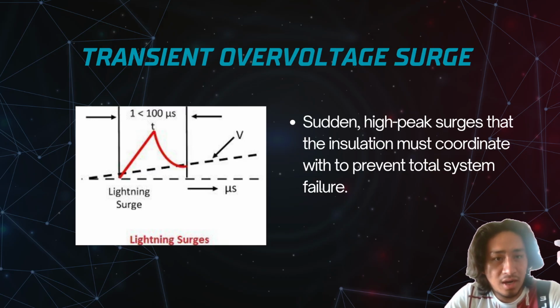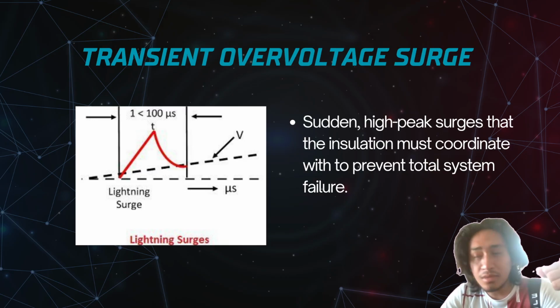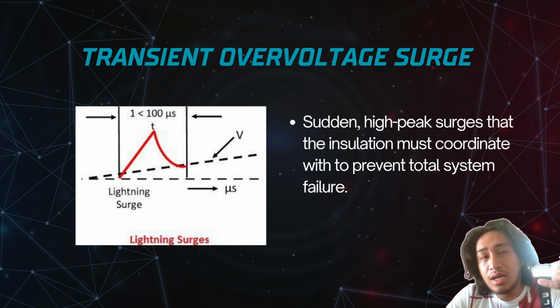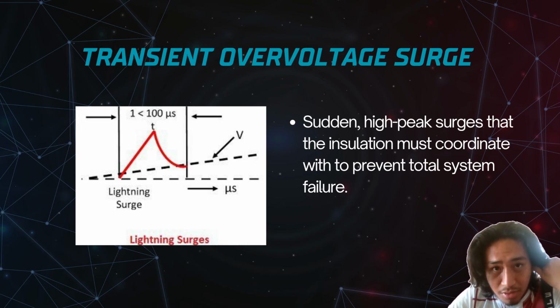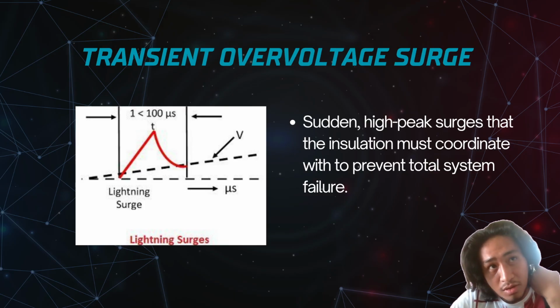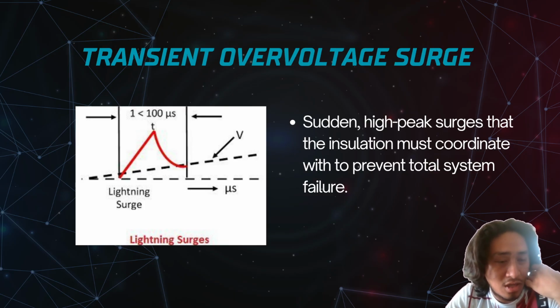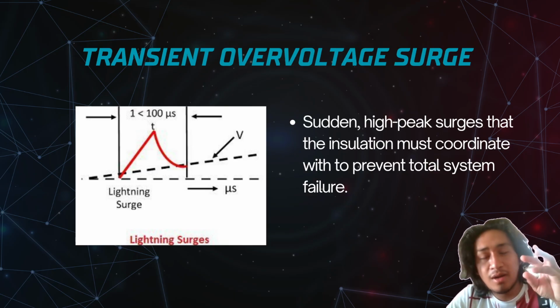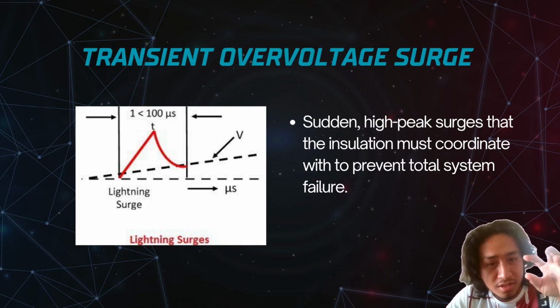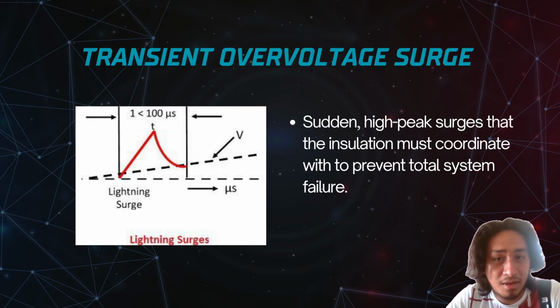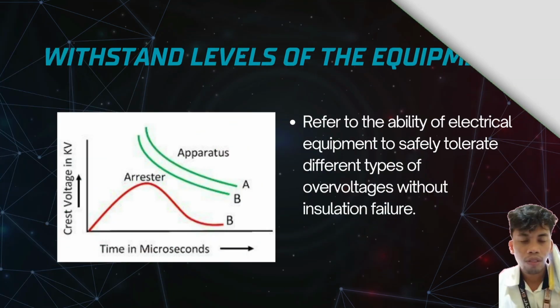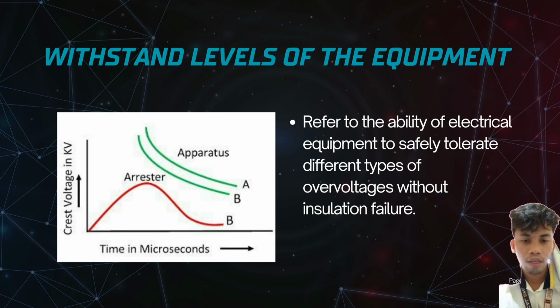So in order for the lightning not to strike the line directly, the tower is equipped with protection called lightning arresters. It is connected directly to the ground to provide a low resistance path to protect the system. The core concept is the withstand level. The withstand level is the maximum voltage an electrical device, like a transformer or motor, can handle before its insulation breaks down and it short circuits.